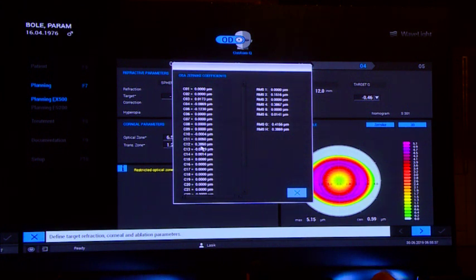So you see it's 0.38 now, and you see how these Zernike polynomials depend on each other. It went from 0.41 down to 0.38. Actually, I need to add a little bit again and compensate again until I have the minus 0.4. But what I want to tell all the delegates here is, for a mathematician, it looks very easy to play around with this. As a clinician, we are always worried about what would happen to the patient if we go wrong.